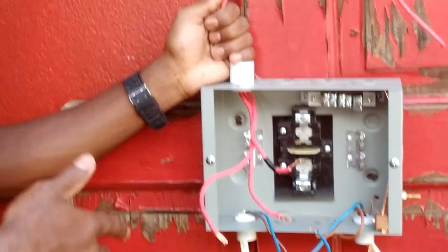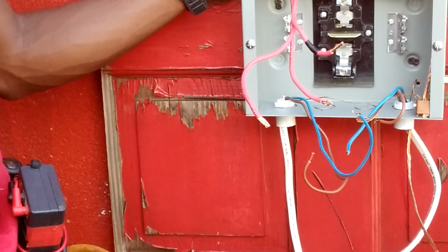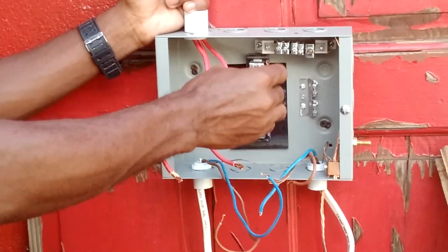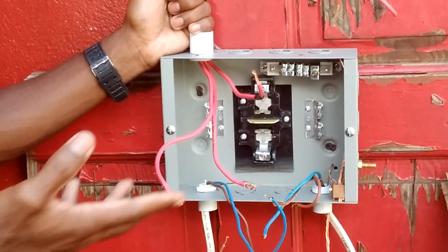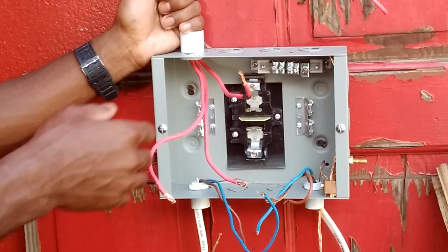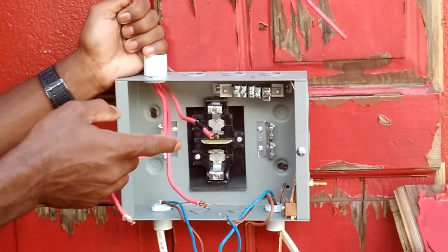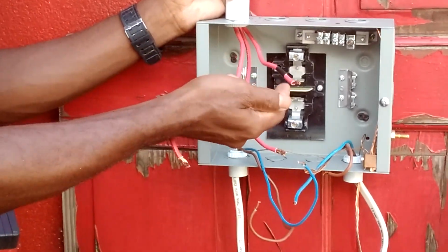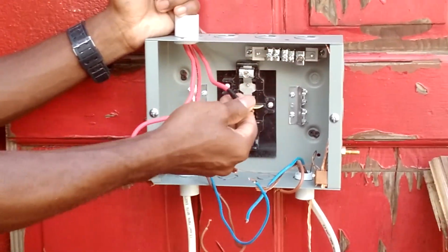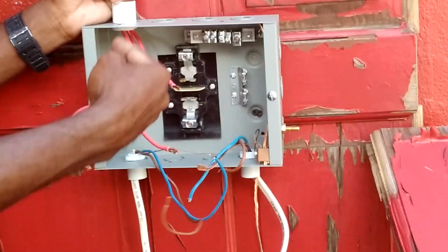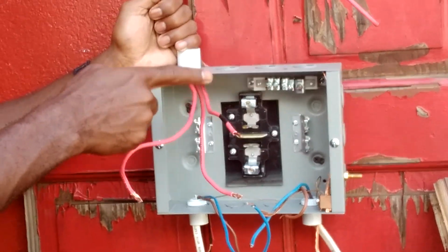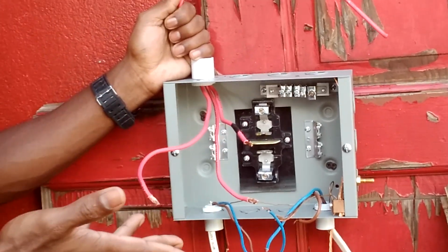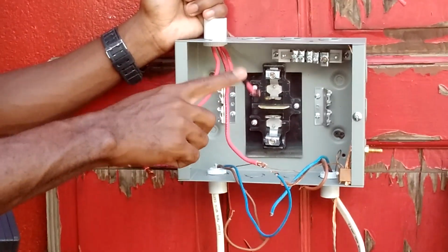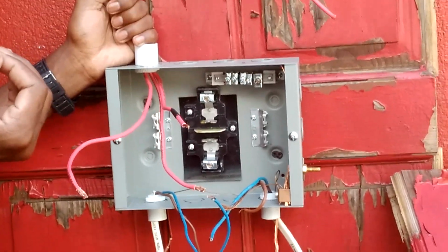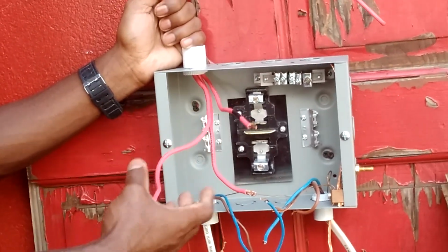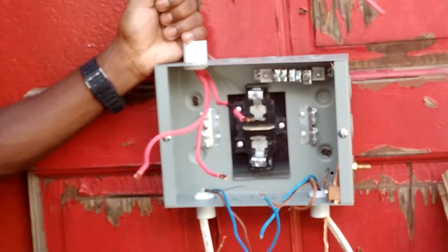In many cases, Jamaican standards for the live wire would have 2 red wires and a black wire. We don't have a black wire today, so that's alright - you can wire a house with 3 red wires as long as you label which one is the neutral. I've already labeled this by wrapping black electrical tape at the end near the termination, so any electrician or inspector coming to inspect the building would know that I used this wire as my neutral wire. So the 2 wires without the black sleeving would be my 2 live wires.